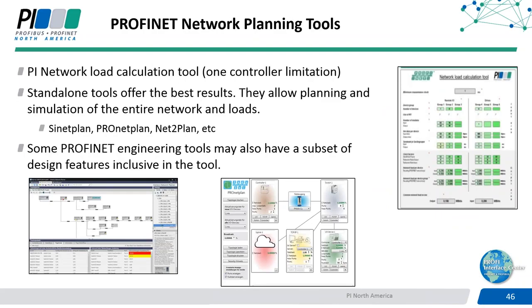Now, to help with network design, there are a variety of tools available, some free, some commercial, which can help in the process. PI offers a free network load calculation tool, which lets you estimate the PROFINET load on one controller at a time, adjusting for the number of devices, update time, and so on. That only considers the PROFINET protocol network load, not other types of traffic such as TCP/IP or other devices you might have out there. So other standalone tools will offer the best results, as they let you estimate not only the PROFINET load but also load from other TCP devices like HMIs, IP cameras, vision systems, SCADAs, and other types of devices.